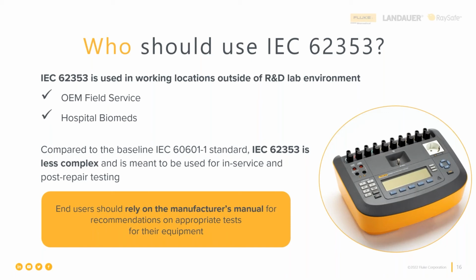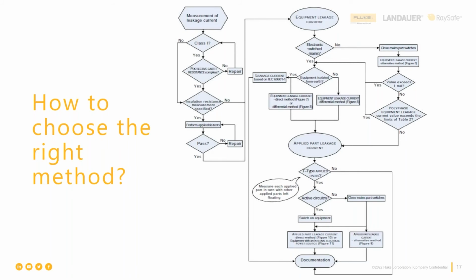So this standard, the tests are shorter. There are fewer steps in the test, and the testing limits are very close, very similar to the IEC 60601-1, but there are 3 different testing methods, and we have to choose which one we're going to use. So how do we do that? Well, in the standard, there is this decision tree.